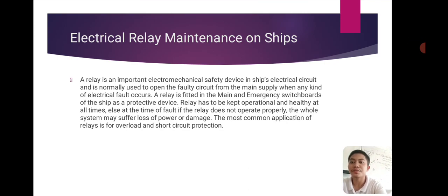Electrical relay maintenance on ship. A relay is an important electromechanical safety device in a ship's electrical circuit, and it is normally used to open the faulty circuit from the main supply when any kind of electrical fault occurs. A relay is fitted in the main and emergency switchboard of the ship as a protective device. Relay has to be kept operational and healthy at all times. Else, at the time of fault, if the relay does not operate properly, the whole system may suffer loss of power or damage. The most common application of relays is for overload and short circuit protection.